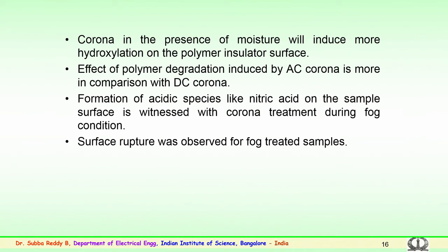The effect of polymer degradation induced by the AC corona in comparison to DC corona is higher. So, experiments have been carried out for both AC and DC voltages, and the comparison has been made, and the degradation effect in particular is seen to be higher when AC corona is applied on the sample in comparison to the DC corona. This is because the surface charging, the space charge which is being formed on the surface, could be one of the reasons for the lesser degradation in comparison to the AC corona.